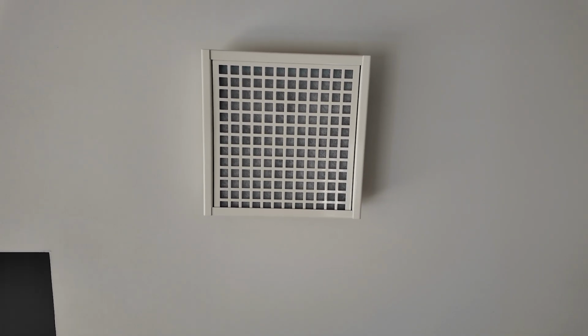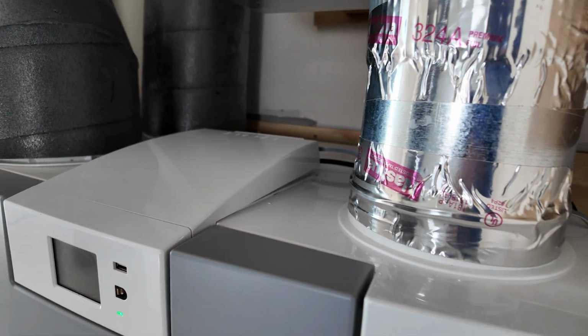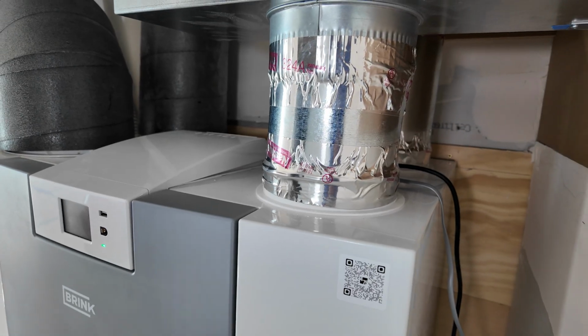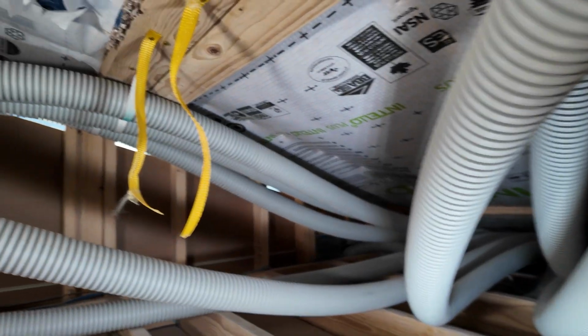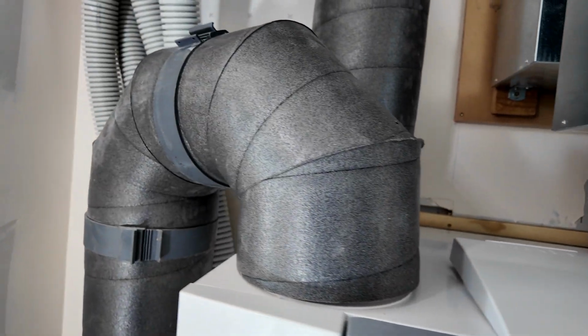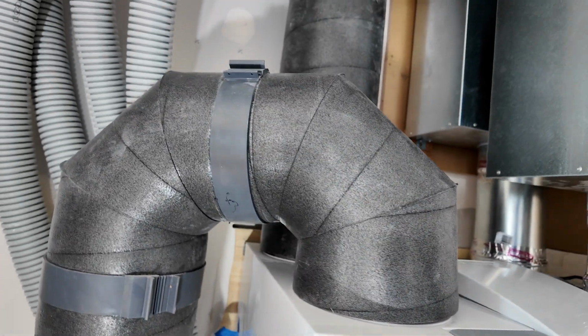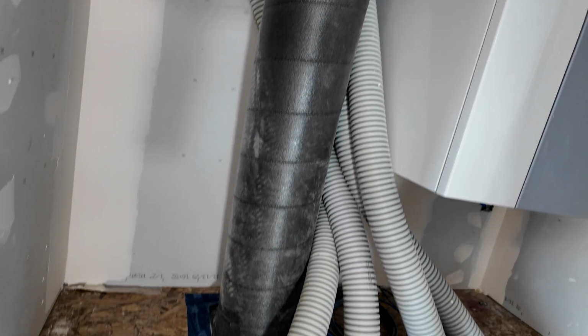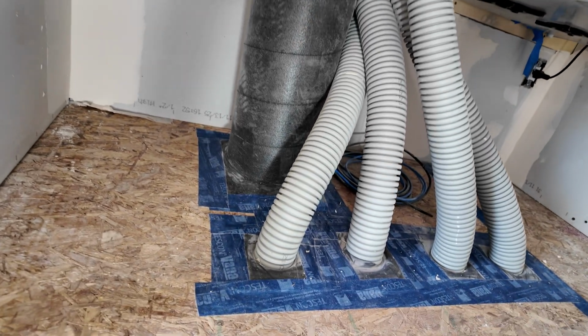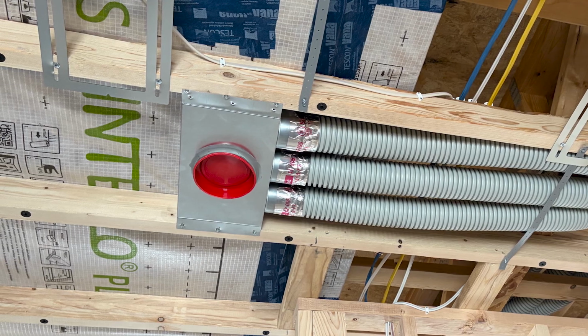Now the commissioning agent should review the overall install quality and document any potential issues. Take photos of any damage to the unit or ductwork, as well as any harsh bends in the ducts. Make sure all connections are secure and airtight. Some of this can also be confirmed once the unit is running by feeling for air leaks at the connection points.